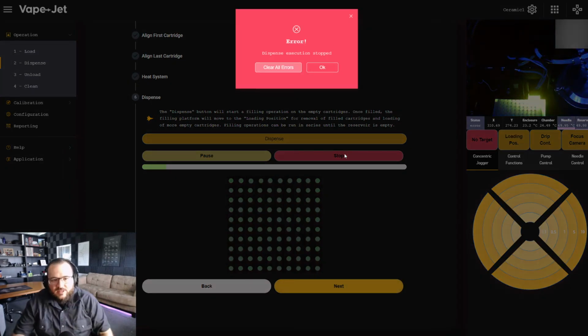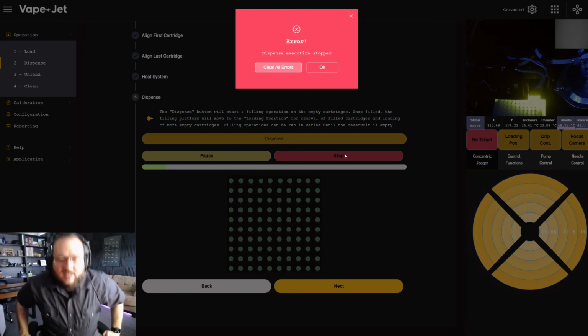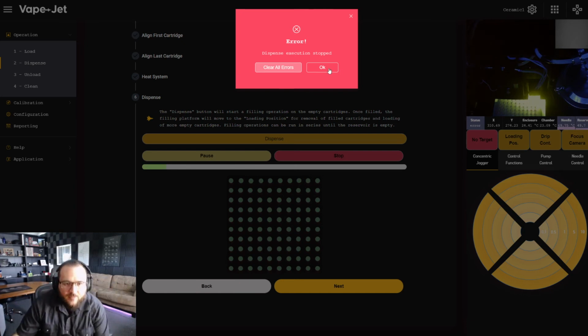Now I'm going to stop the system here so we can move on and demonstrate other functions. One thing I'd like to point out is that now that I've introduced air into the system, the internal lights of the VapeJet system have turned red. The LED indicators show the operator what status the machine is in: green means it's ready to be loaded, red means there's an error, and blue means it's running.